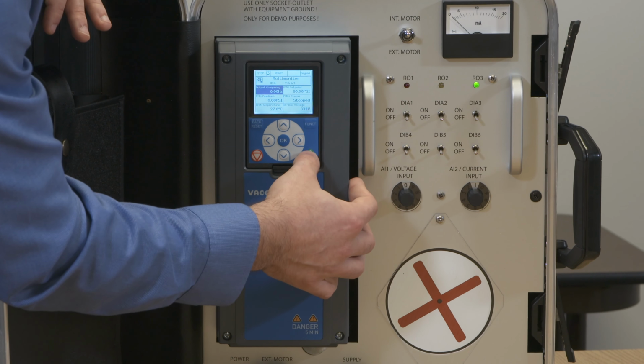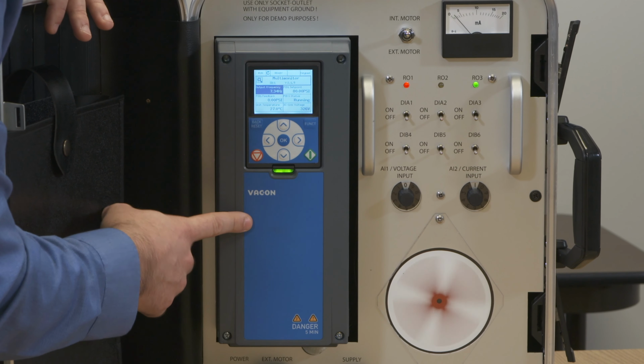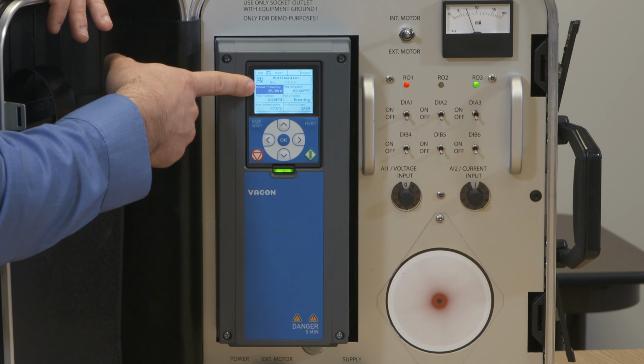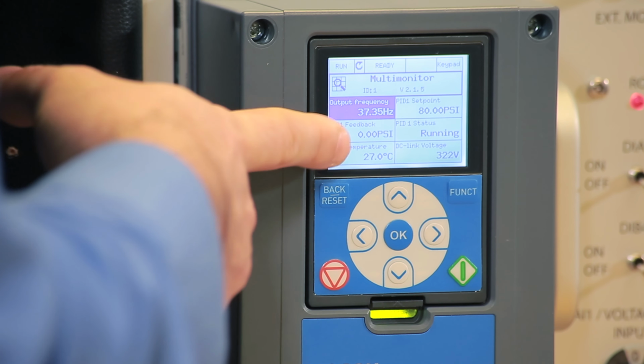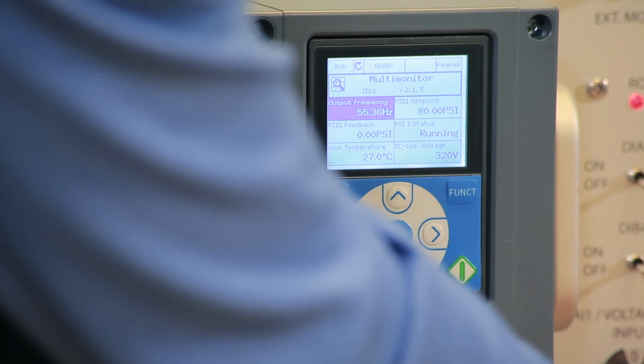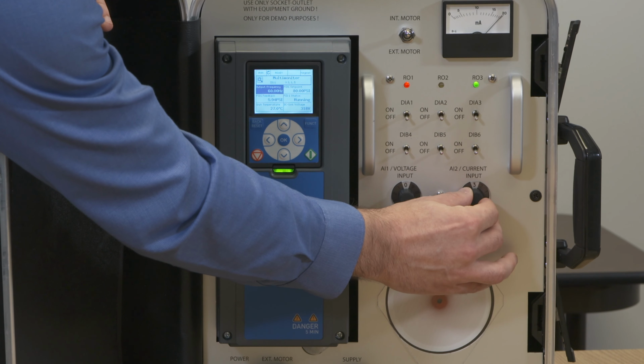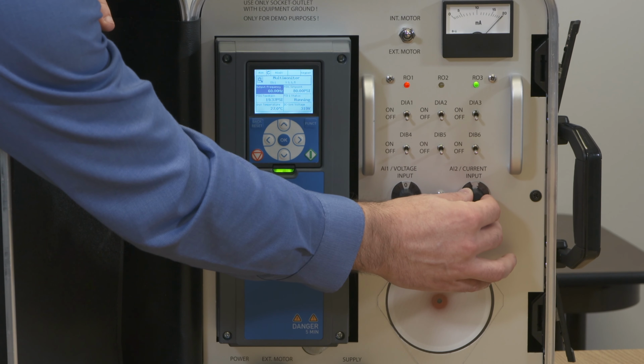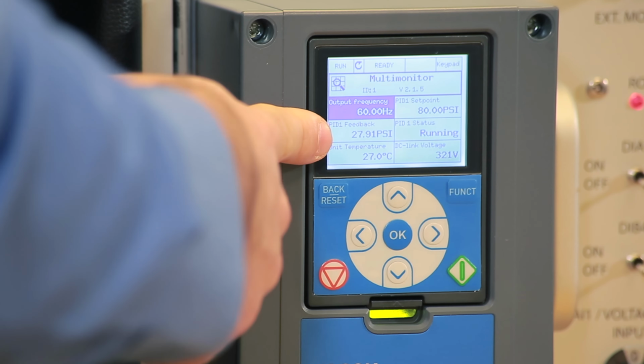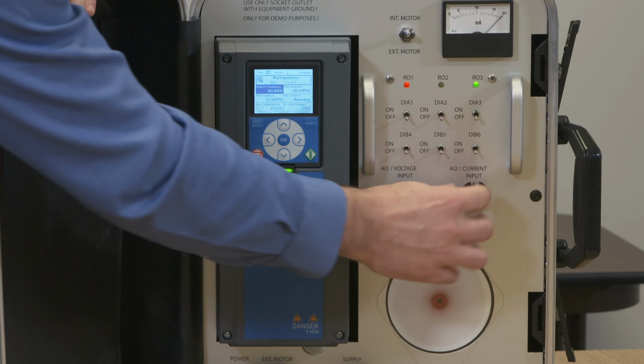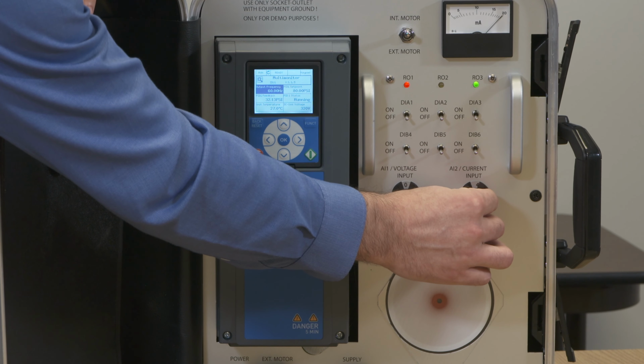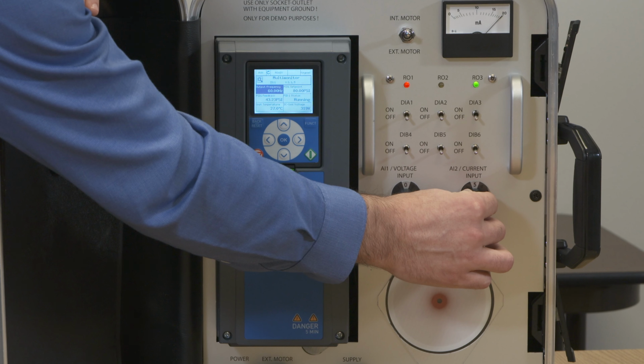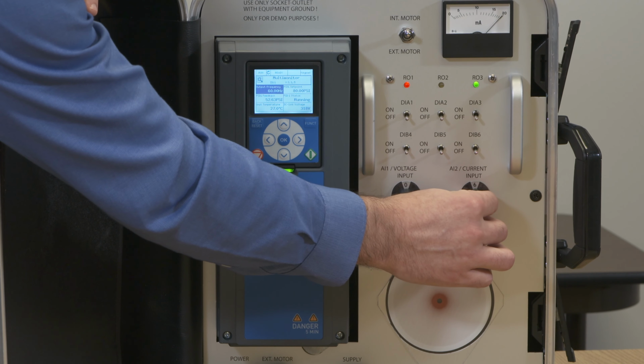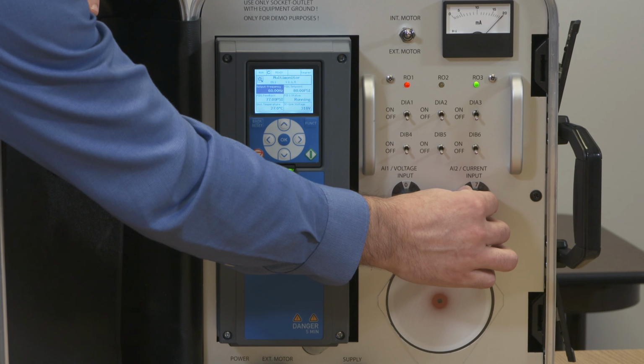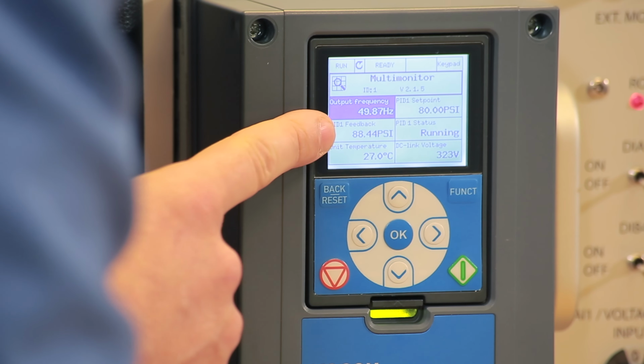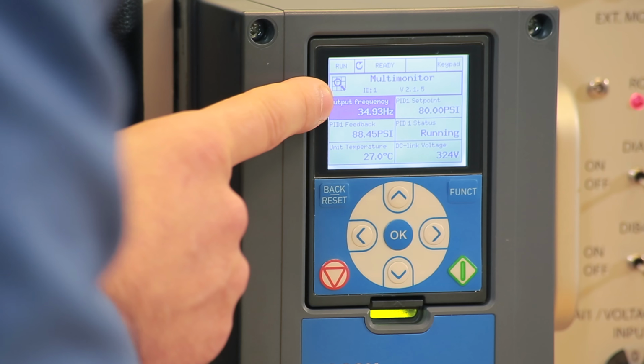So we want to run it. Let's press run and the drive will accelerate, as we see here, output frequency. And now we're going to start changing the actual feedback. So we're filling up the water pipe here. The PID feedback increases and we want to get this over 80 in order for the drive to slow down. We're increasing it. And once the feedback goes above 80, the drive immediately slows down.